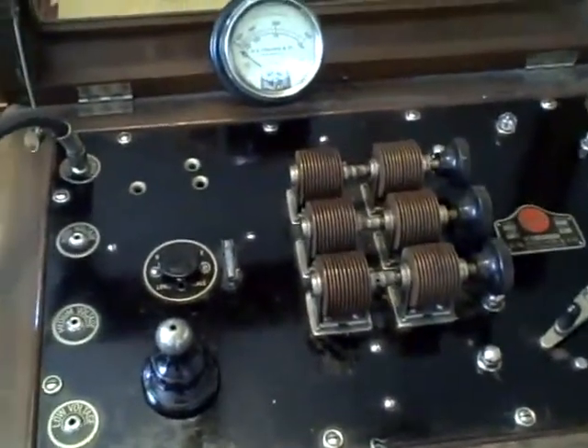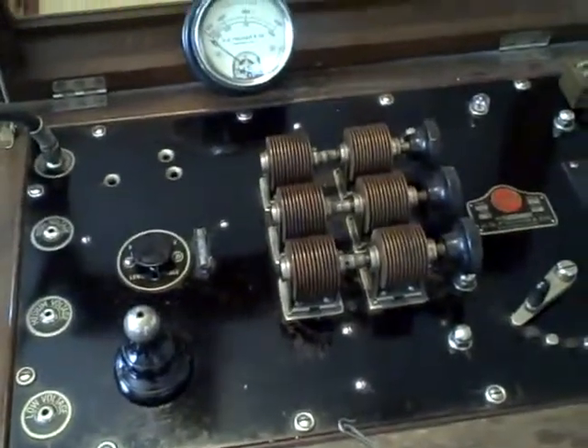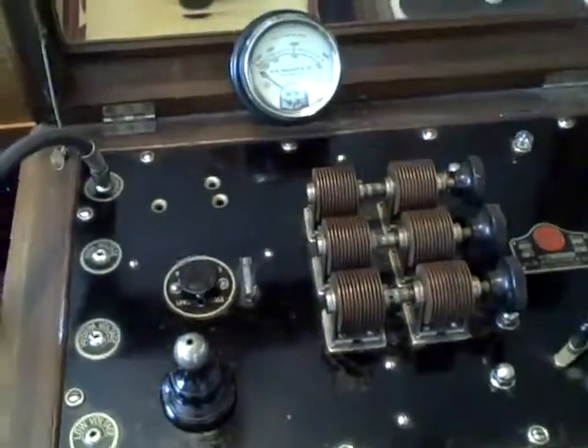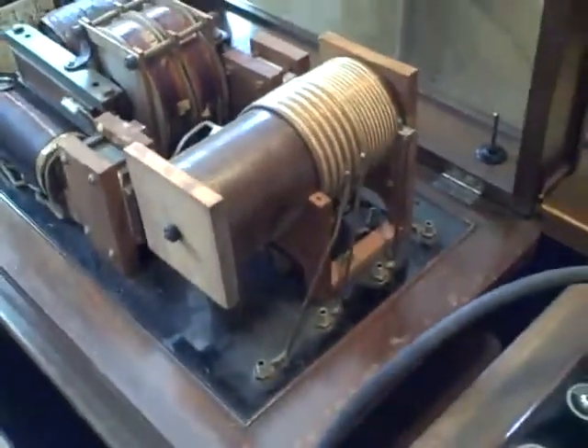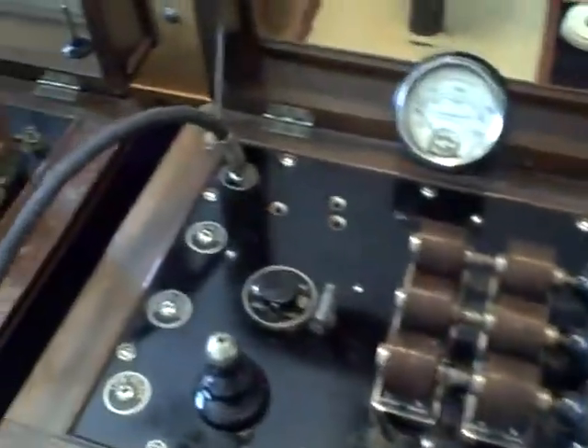But the Fischer Type G diathermy was probably the most popular, and today is amongst collectors because they're a simple machine, yet very elegant in appearance, and the construction is simply superb inside. And I have two machines here side by side so that we can take a look at both the internal and external components. And if we start off to the left, you'll see a variable reactance coil. And this limits the current from 1 to 5 amps from the wall. And it's selected on the outside by this simple rotary switch.